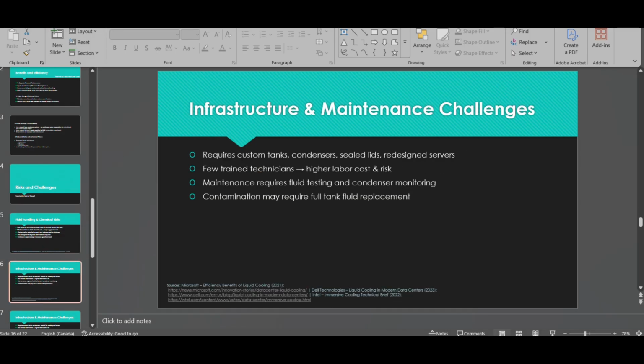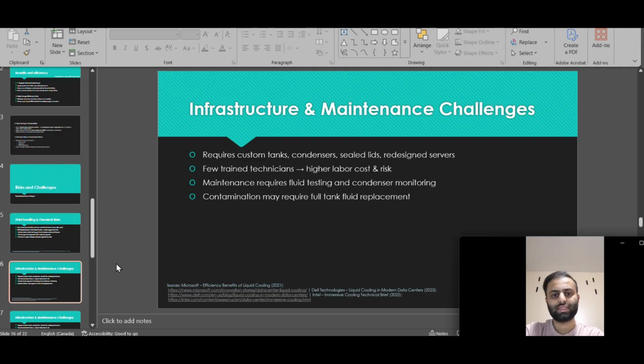Another challenge they face is infrastructure and maintenance. Two-phase immersion requires specialized hardware, sealed tanks, and condenser systems that traditional data centers don't use, so most off-the-shelf servers are not immersion ready. Microsoft had to partner with certain vendors, like Wiwynn, for custom equipment. From a maintenance standpoint, technicians also need new training, because working with boiling dielectric fluid is very different from air-cooled racks, and tasks like fluid testing, condenser checks, and tank sealing introduce new operational complexity.